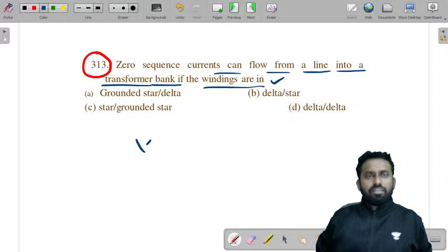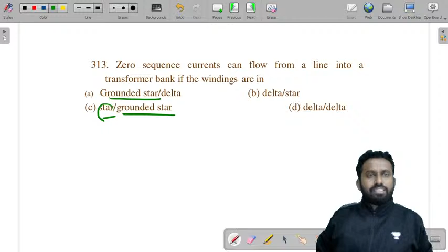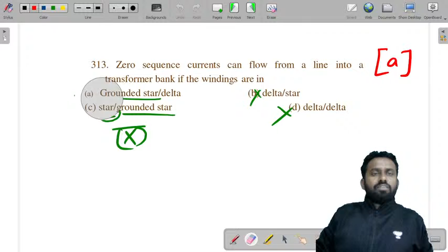Zero sequence currents can flow from a line into a transformer bank if the windings are - it should have a star with a ground, right? Let's try to look at this. You have a star and a ground, grounded star, and grounded star and star. This is star and star, so invalid. So you do not find any grounded star here. So the only option is A. The answer to this question is A. Now let's look at the next question.